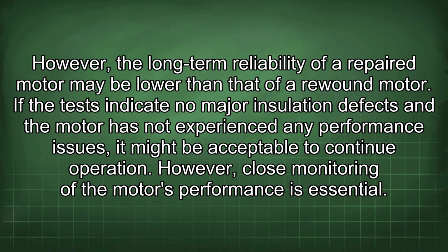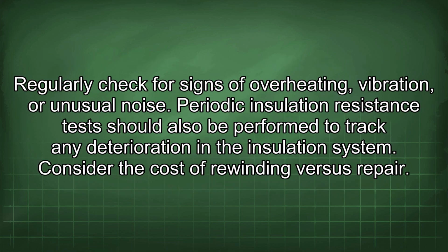If the tests indicate no major insulation defects and the motor has not experienced any performance issues, it might be acceptable to continue operation. However, close monitoring of the motor's performance is essential. Regularly check for signs of overheating, vibration, or unusual noise. Periodic insulation resistance tests should also be performed to track any deterioration in the insulation system.